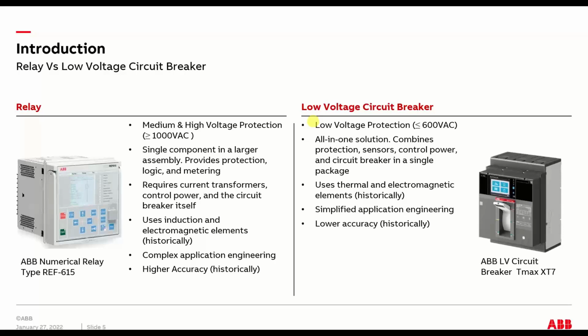So, relay versus circuit breaker: relay for medium voltage, and the molded case circuit breaker and low voltage circuit breaker for under 600 volt applications. The big difference is that the relay is one component in a larger engineered system, whereas the low voltage breaker is an all-in-one solution, basically pre-engineered. I don't like to say plug and play, because there's still a lot of engineering that goes into it, but you pick up your breaker, and all its ratings and everything are pretty much predefined, and all the parts you need are included in the package that you buy.